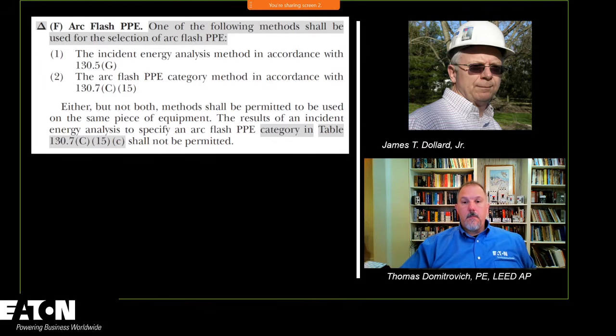It works. But when you do an incident energy analysis and you come up with 7.5, and then you say we're going to put a guy in an 8, well now he might be exposed at 10 because it's not a perfect science, and he's wearing 8. Another problem is the engineer could come out with 8.2. Now he says, well, we'll put you in arc flash PPE category 3. Now you got a guy wearing a 25 cal suit, most likely, when he should really be wearing a 12, something like that, shooting at 150% of the exposure.